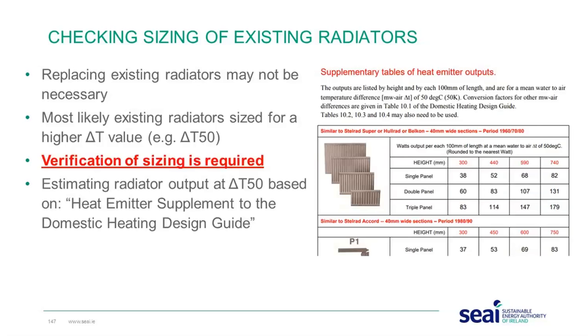So how would you go about doing it? Well, there's the supplement to the domestic heating design guide. There's a heat emitter supplement to it. That will give us typical radiators on sale during a period, and it will give us the estimated output of those radiators. So we can match them up visually and by eye and so on. And that will give us an estimate of what the output of that radiator is. Then we need to apply a conversion factor.